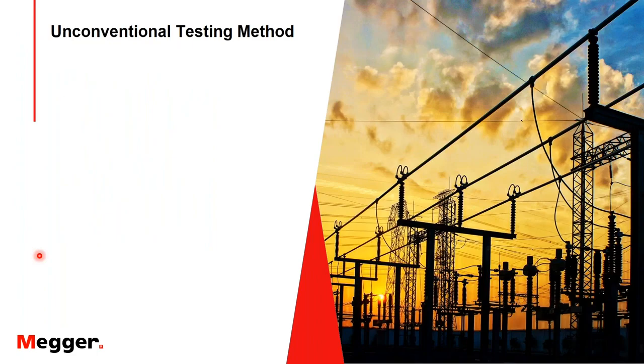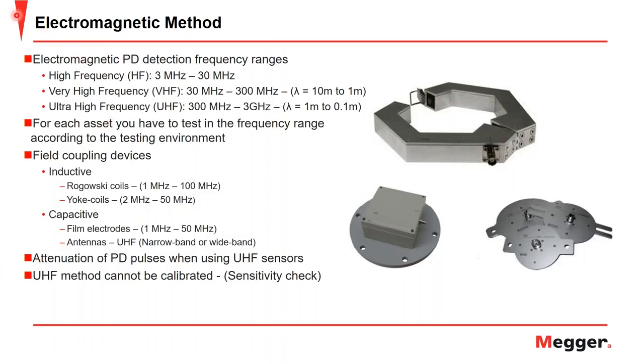So now that we've covered the conventional testing method, let's move into the unconventional testing methods. First, we'll discuss the electromagnetic testing method, where PD detection is done by electromagnetic transients that are captured by means of inductive and capacitive sensors, as well as specially designed field probes. When we talk about these sensors, the PD detection has different frequency ranges. These can range from high frequency, or HF, at 3 megahertz to 30 megahertz, to very high frequency, or VHF, at 30 megahertz to 300 megahertz, which corresponds to wavelengths between 10 meters and 1 meter.